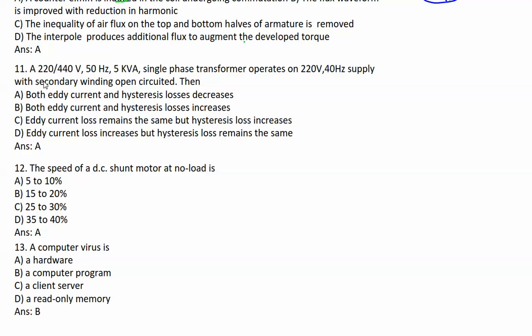A 220/440V, 50Hz, 5kVA single-phase transformer operates on 220V 40Hz supply with secondary winding open-circuited. What will be the losses? Generally, eddy current loss is proportional to Bmax^1.6 × f. In this case, we are reducing the frequency. If Bmax is kept constant - remember this condition - if Bmax is kept constant, the ratio V/f is kept constant.